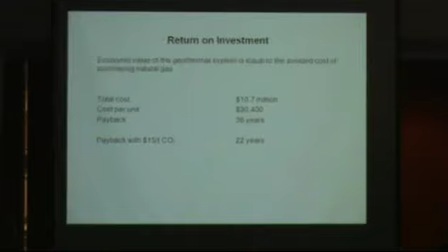The economics of this is based on the avoided cost of natural gas. We've made many assumptions, and we've come up with a payback on this system of 36 years. Just out of interest, we looked at how much value including a CO2 emission avoided credit would add, and it reduces that down to 22 years. Again, I'm not suggesting that could happen, this is just part of the conversation.